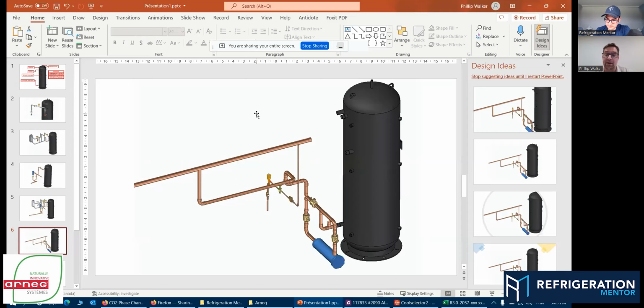Some designs will have a plate heat exchanger, right? So we want to remove those types of inefficiencies. And especially if we have oil pooling, we're going to have oil coming down on this line over here and clogging up this valve. So through some laboratory testing, you'll see our systems. And that's a question we get a lot when we're doing startup: hey, looks like you did this for a reason, and you put the outlet down here on the flash tank at exactly this location for a reason. Well, yeah, you're right. We did.